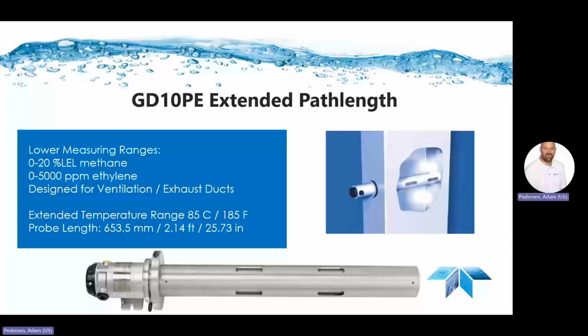Monitoring fresh air intake, which feeds control rooms, maintenance garages, and other buildings with human occupancy, for hydrocarbons is a necessary safety precaution in facilities like oil refineries and petrochemical plants. The GD10PE is designed for these critical applications involving large volumes of air with high velocity. The extended measuring chamber makes the GD10PE uniquely suitable for the large areas of these HVAC intakes.